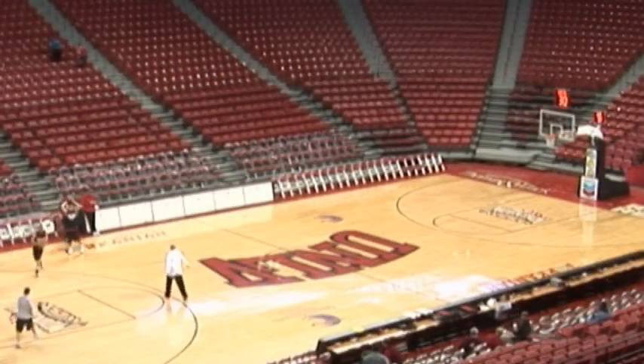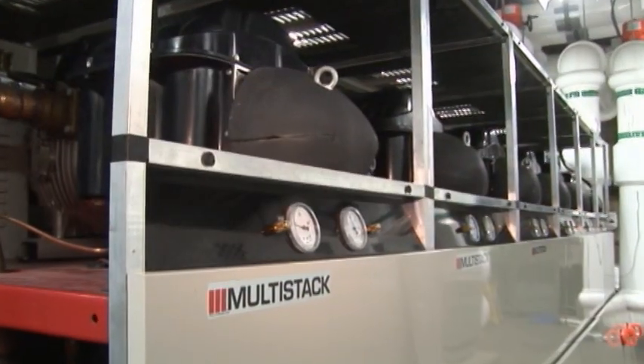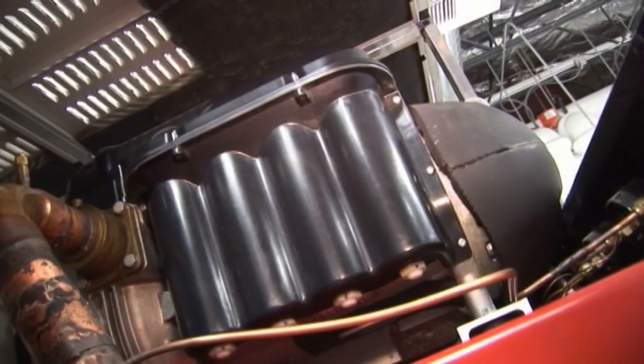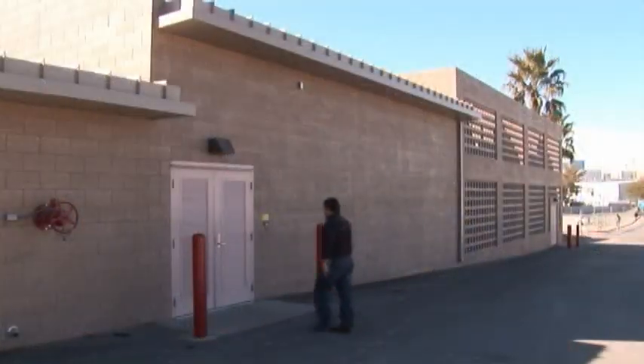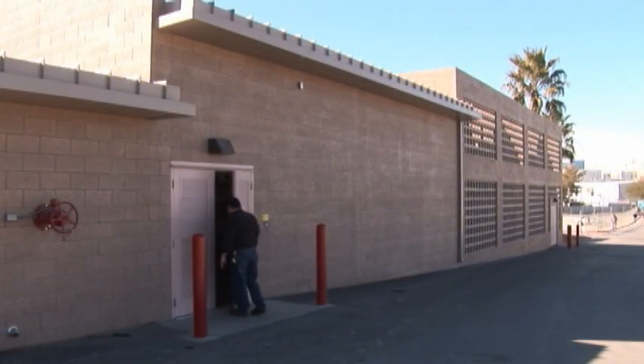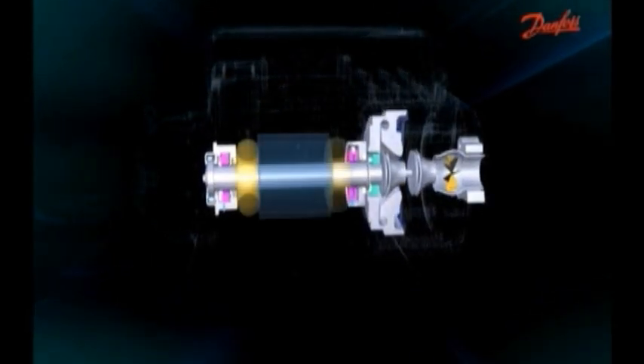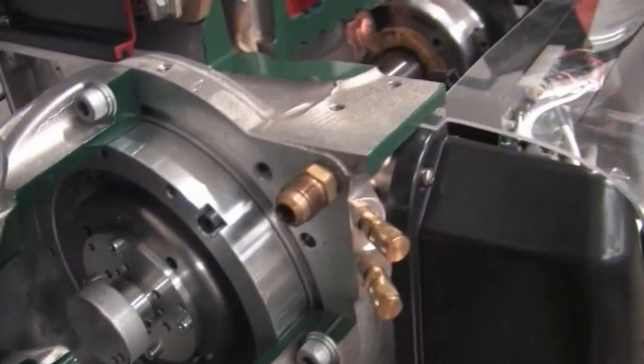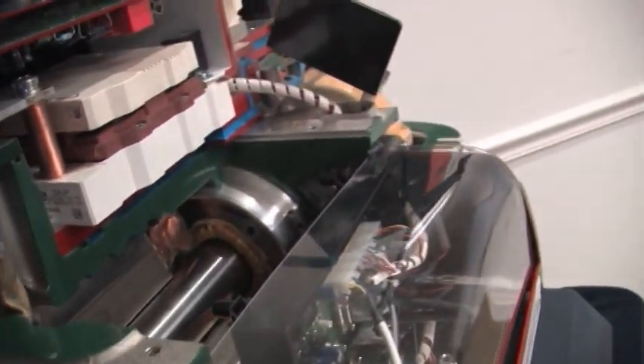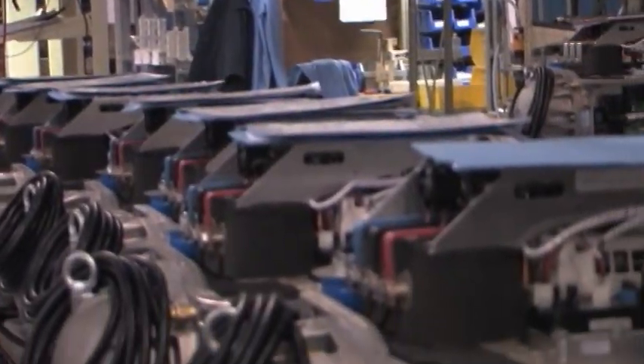It will go from an 18,000 people venue down to just office people. It's where before we had two 500-ton chillers, and they would run at 500 tons. We'd be only needing 150 tons. To me, it was a waste of energy. Now with these Turbocors, we can run precisely that 150 tons to cool a building. The ability to operate at partial or full capacity allows control of the motor's speed and inlet guide vanes to match the demands of the system. This produces optimum energy-efficient performance and savings.